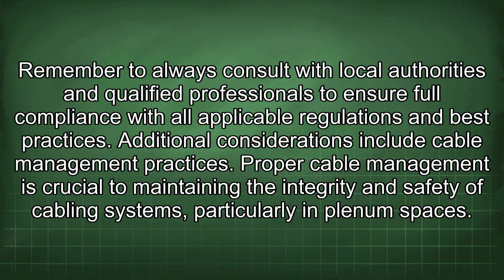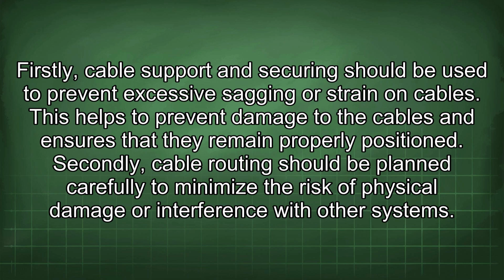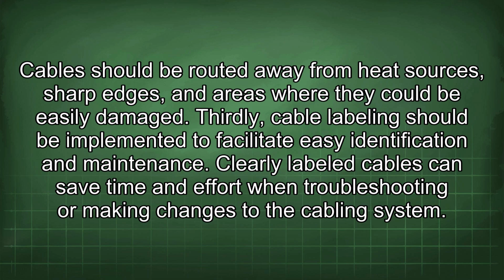Proper cable management is crucial to maintaining the integrity and safety of cabling systems, particularly in plenum spaces. Firstly, cable support and securing should be used to prevent excessive sagging or strain on cables. This helps to prevent damage to the cables and ensures that they remain properly positioned. Secondly, cable routing should be planned carefully to minimize the risk of physical damage or interference with other systems. Cables should be routed away from heat sources, sharp edges, and areas where they could be easily damaged. Thirdly, cable labeling should be implemented to facilitate easy identification and maintenance. Clearly labeled cables can save time and effort when troubleshooting or making changes to the cabling system.